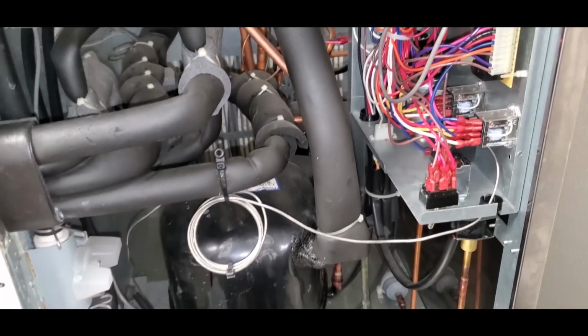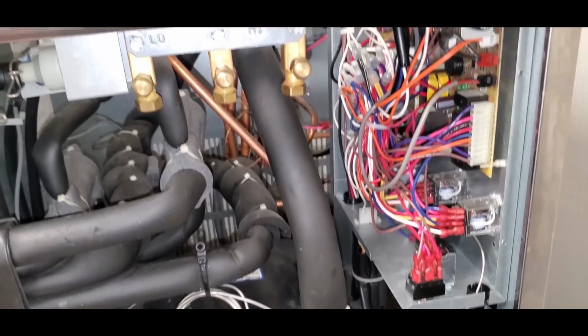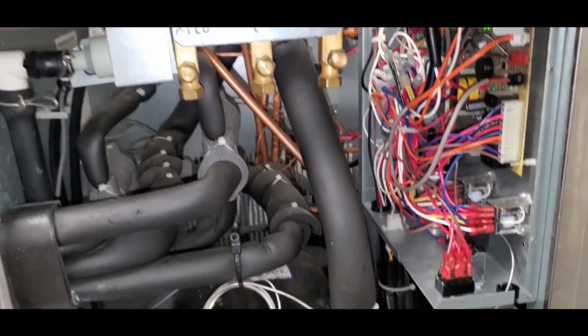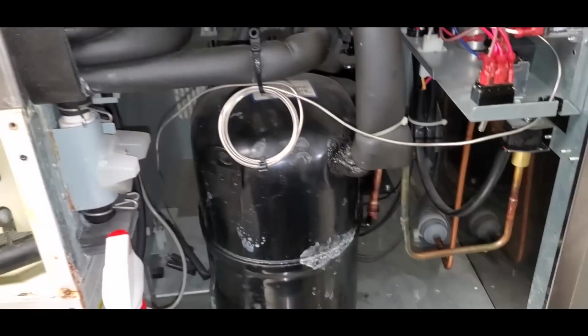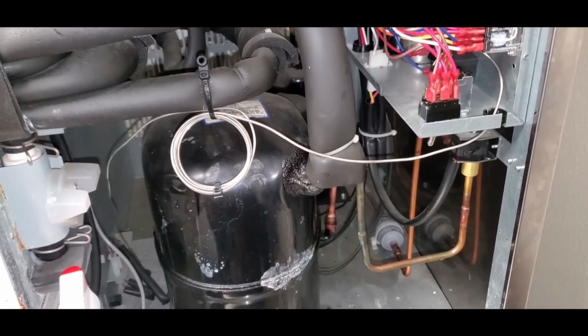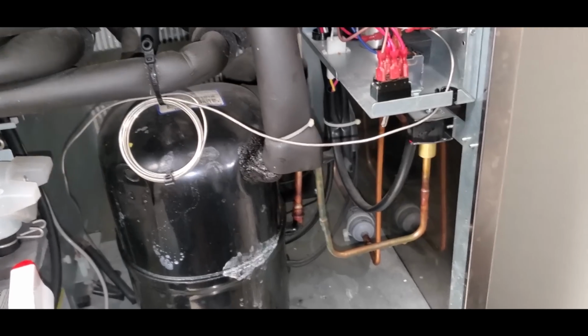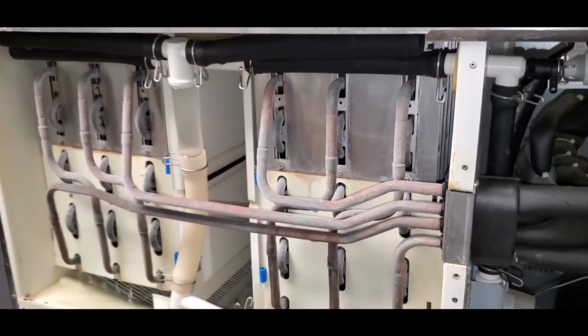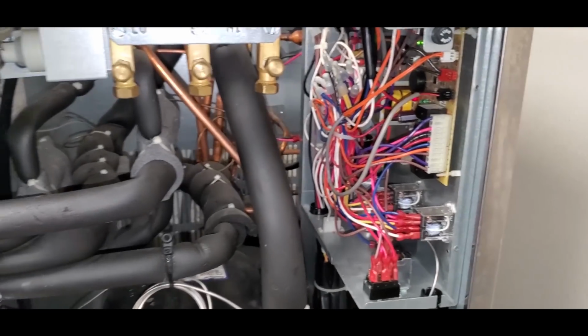But my fear is I still don't know, again, they're saying single beep. I mean, a leaking hot gas valve is not going to cause it to run high evap temp, so I don't know. I really want to hear this beeping sound, but I already know that we have leaks. I'm tempted to come back first thing tomorrow morning and reset it myself just so I can hear which safety is going off.